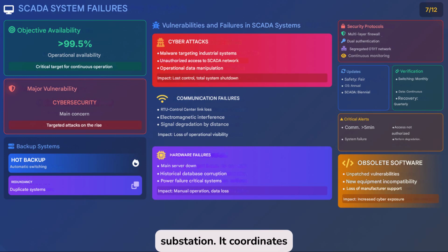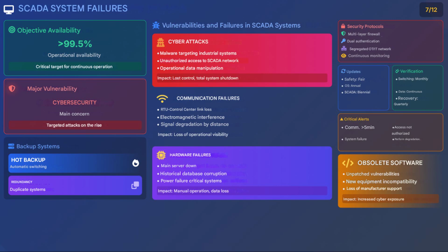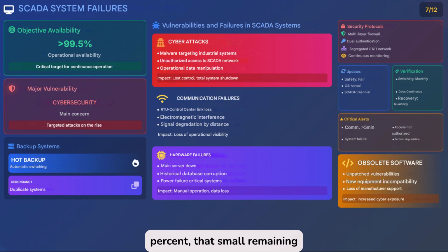It coordinates control, monitoring, and remote operation, allowing real-time response to failures or changes in conditions. Although its availability typically exceeds 99.5%, that small remaining fraction can cause critical interruptions if effective backup is not available, leading to production losses, penalties, or regulatory noncompliance.